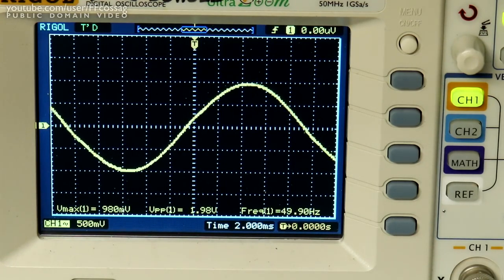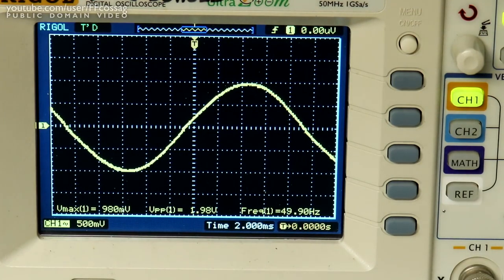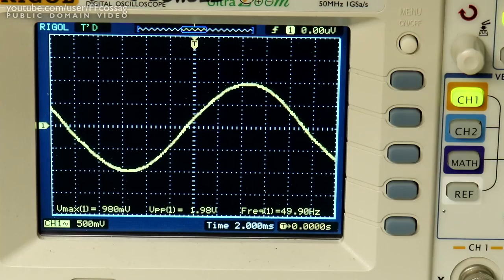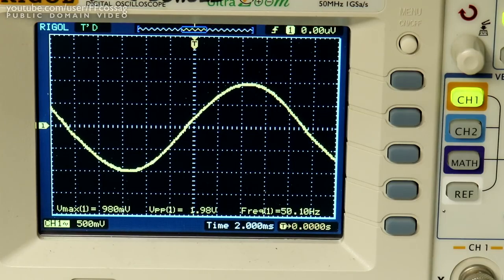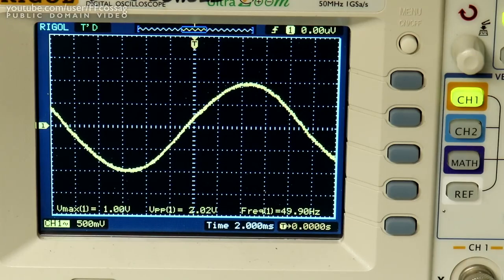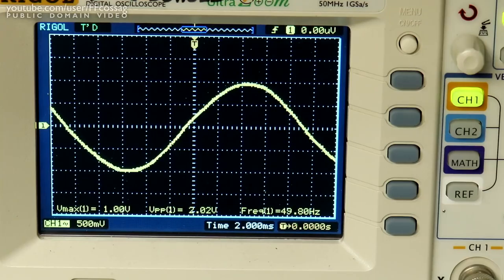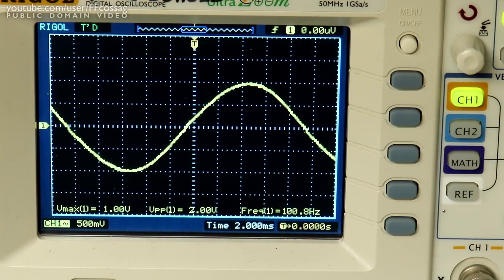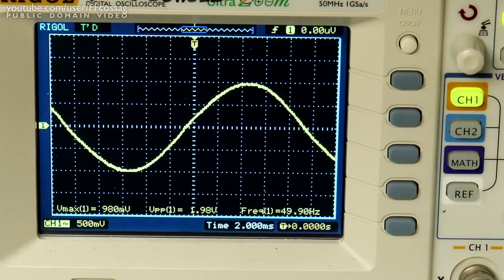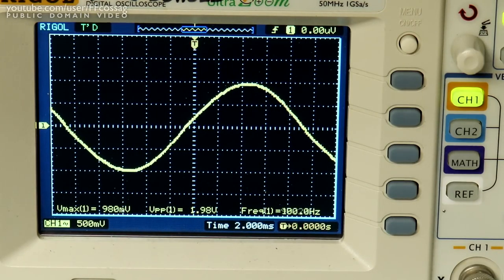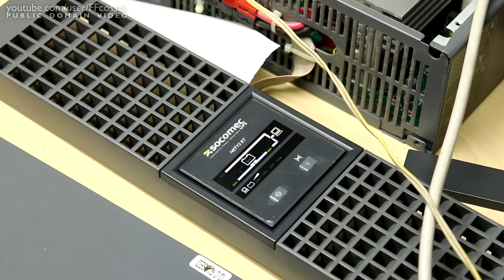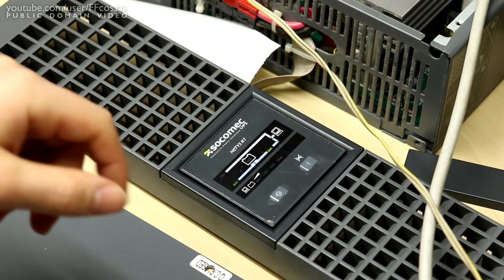In the way the waveform looks, that is what's coming out of the UPS, much much cleaner. To show that this UPS is indeed providing its own sine wave, if we kill the power to the UPS, the sine wave doesn't change at all. We just get an incredibly loud beeper going. The same is true when you plug it back in. It is a very clean switchover since the inverter is running 24 hours a day.